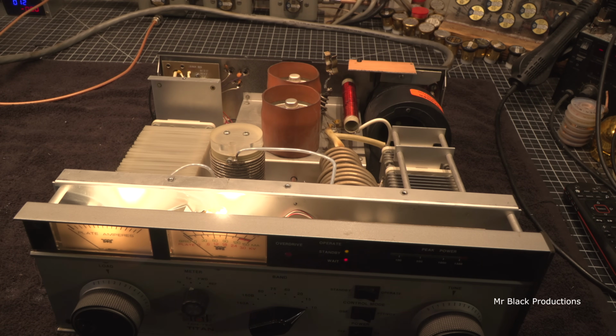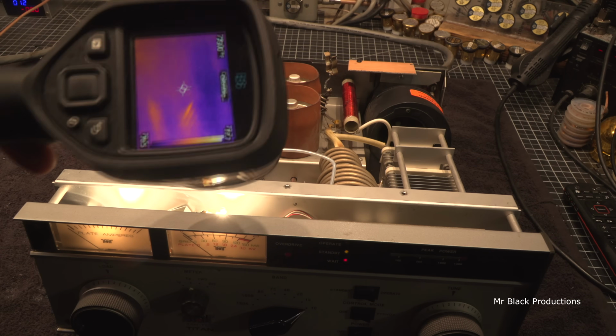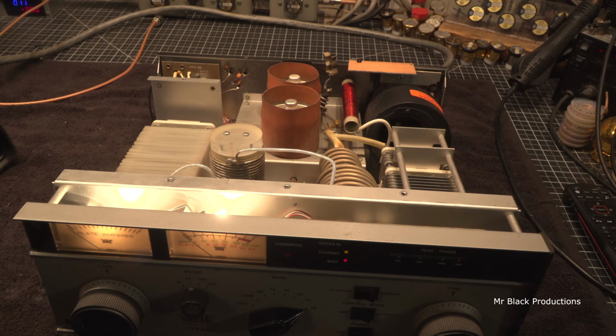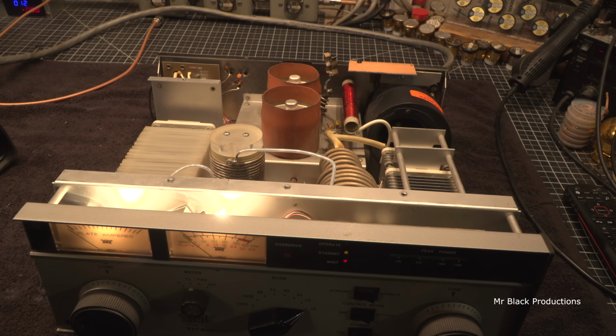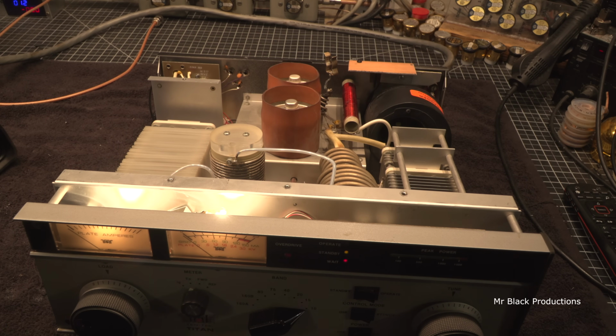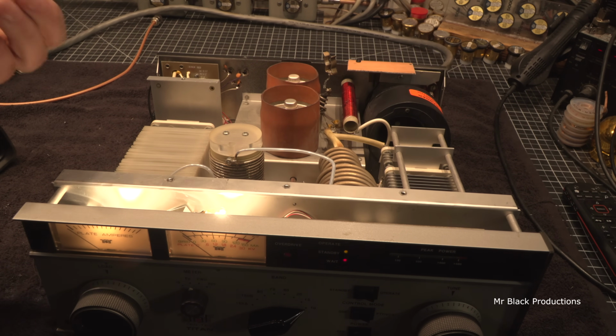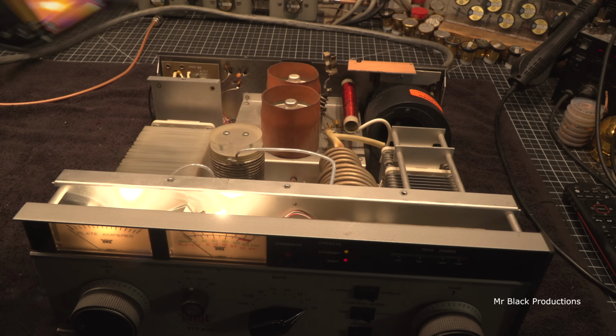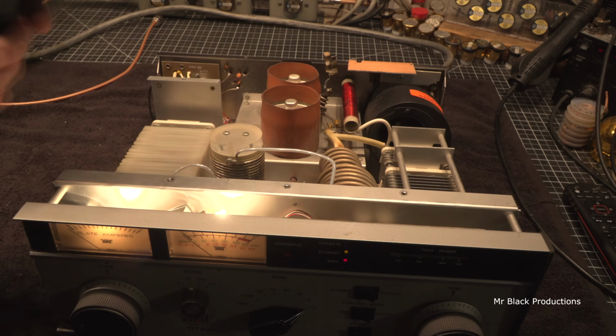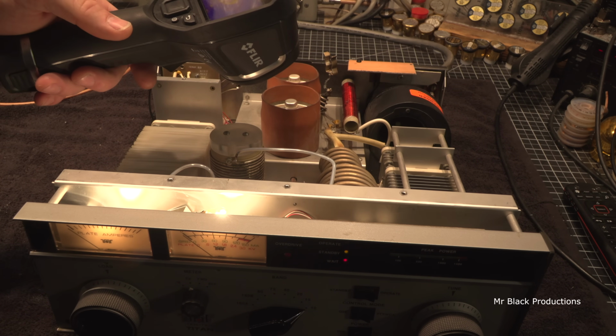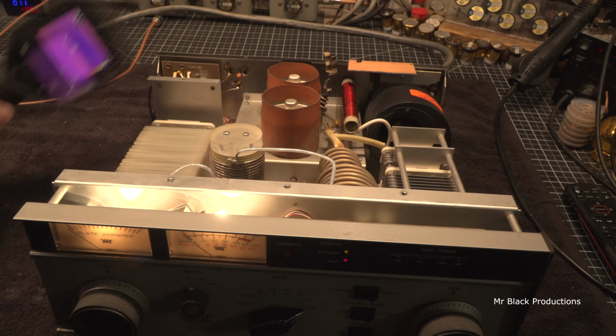The other thing you got to think about is that reflective surfaces have a tendency to emit heat energy in a different pattern than what this gun is able to see. In an ideal world, I would put a certain kind of heat coating on the top of this thing that would emit the infrared energy this gun is trying to measure, and give us a more accurate reading.